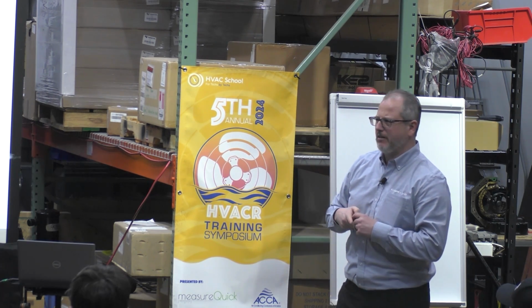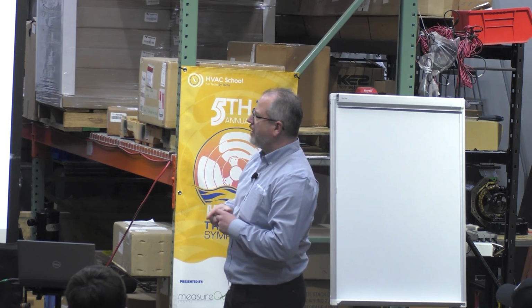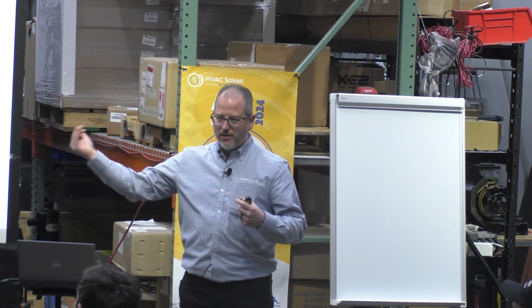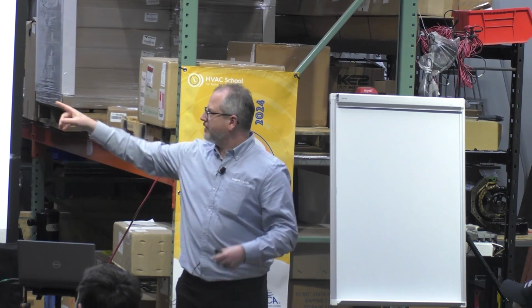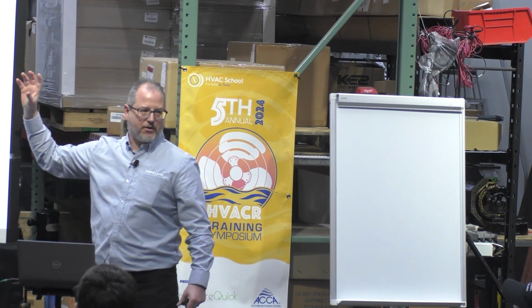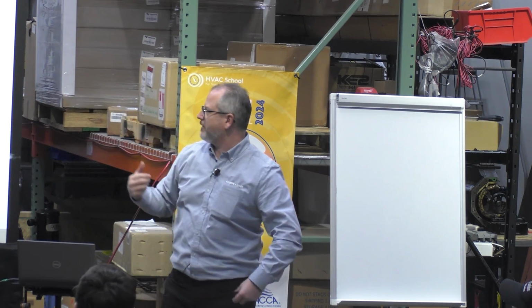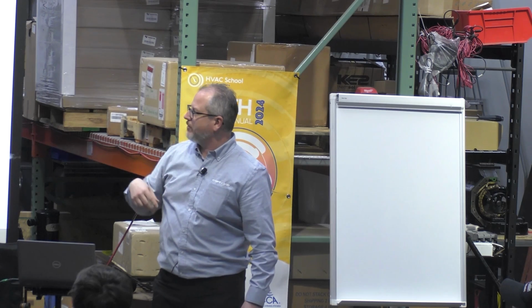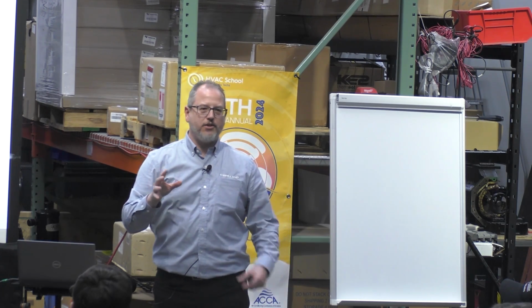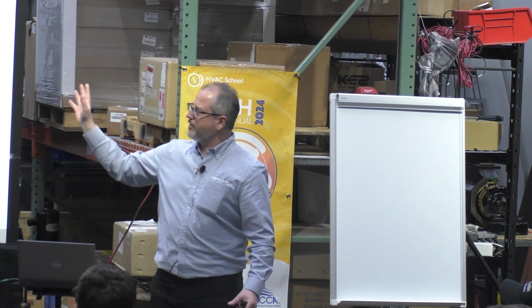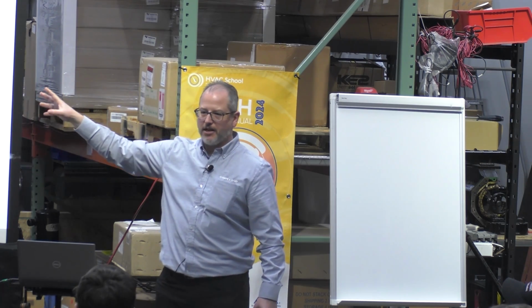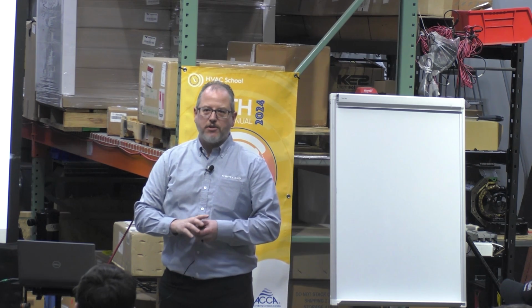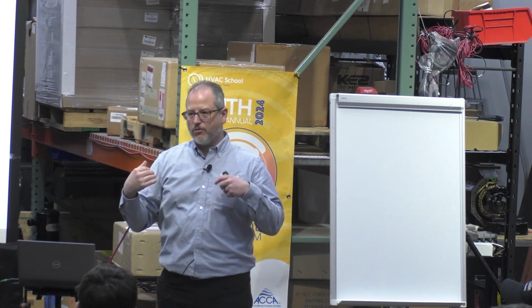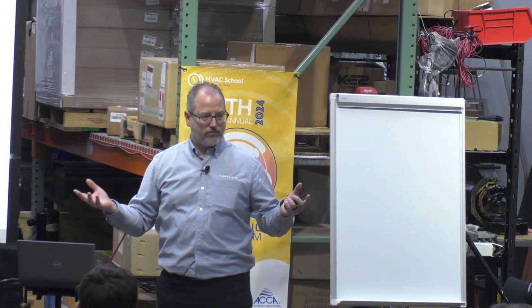So this spring, I don't remember, June maybe, I was in our factory where they do teardowns of warranty scroll compressors. And so they're showing me these compressors that come through. They go through a device that looks similar to this, and it's like a big can opener. A big wheel cuts open the compressor, then it keeps on going through. If the compressor had no problems, it goes to, this is in a different room. So this is a compressor that had no problems, okay? Almost 40% of our compressors that get sent back under warranty, there's nothing wrong with them. Wow, is that high, 40%?